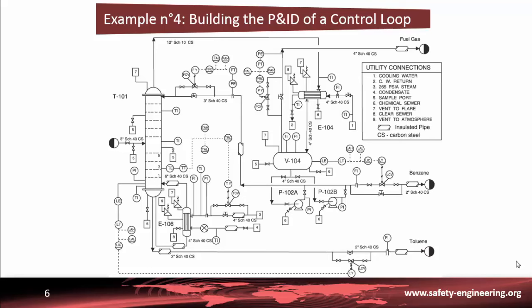In this P&ID diagram, the chemical process described here is based on the hydrodealkylation of toluene to produce benzene as discussed in part 1. The feed for distillation column reaches the middle of the column, in this case, a mixture of toluene and benzene. The product leaving the top of the column is called the distillate. Vapor leaving the top of the column passes through a heat exchanger, called the condenser, where it is partially or totally condensed. The resulting liquid is temporarily held in the accumulator or reflux drum. A liquid stream is withdrawn from the drum and returned to the top tray of the column as reflux to promote separation. The base of the column is typically used as a reservoir to hold liquid leaving the bottom tray.